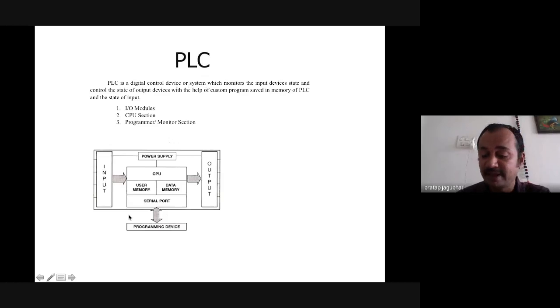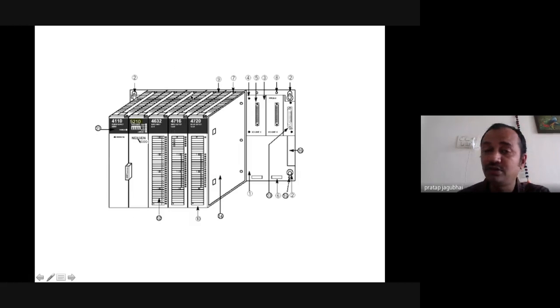Now, before going to the basic function of the PLC, I would like to show some actual construction of how the PLC fits into the room or the control panel, where your motherboard panel will be there. In this motherboard panel, your power supply card, then your CPU card, and then your IO interface will be fit inside, directly mounted on the motherboard, where your communications will happen through the IOs as well as the SMPS as well as the CPU, and it will be online, and you can connect your laptop directly to download the program.